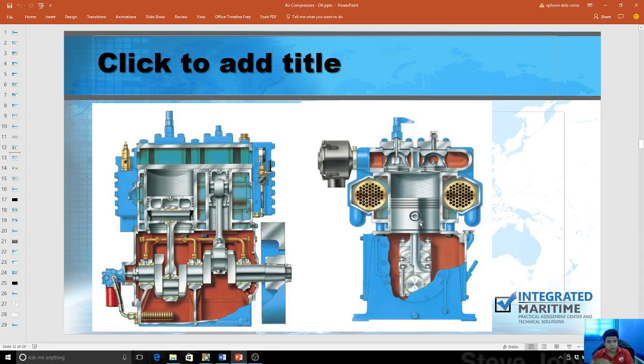It's a reciprocating compressor, meaning it goes up and down with a piston. It has an interstage cooler and everything. It has a filter. So this is how it really works. Air comes in here, is processed there at low pressure, and goes inside to the low pressure side. The bigger the piston, the lower the pressure. Once it goes inside, it goes to that specific cooler. Then it goes to the smaller piston, making it into higher pressure. Then it goes out. Typically, very simple.